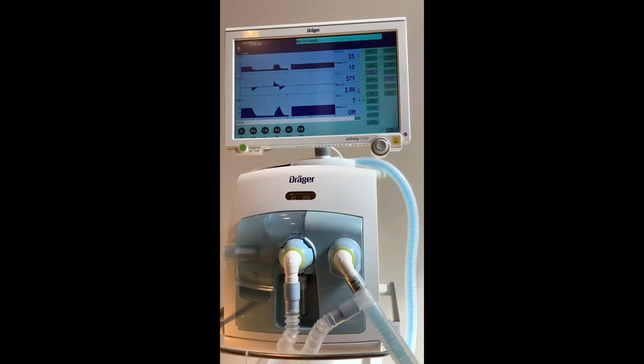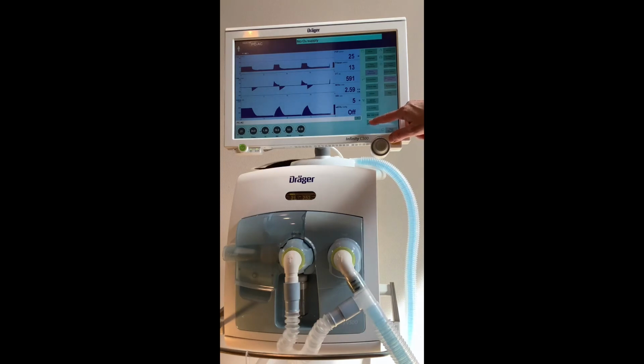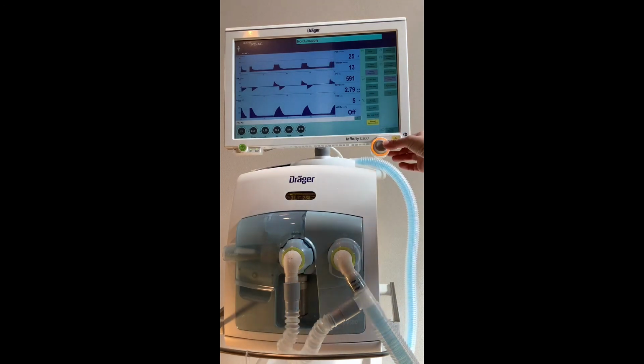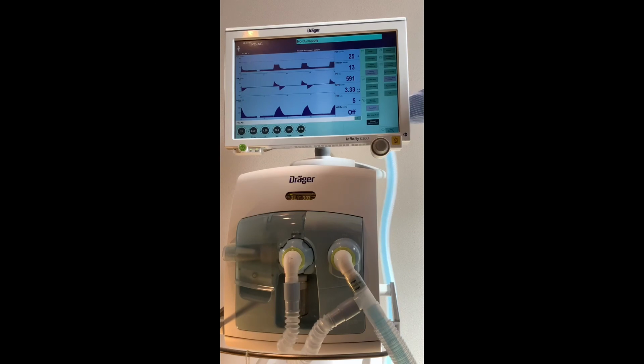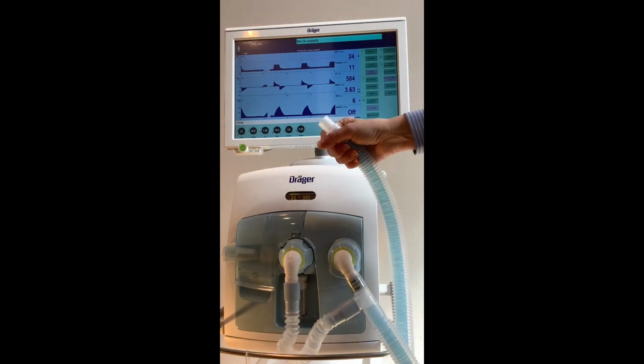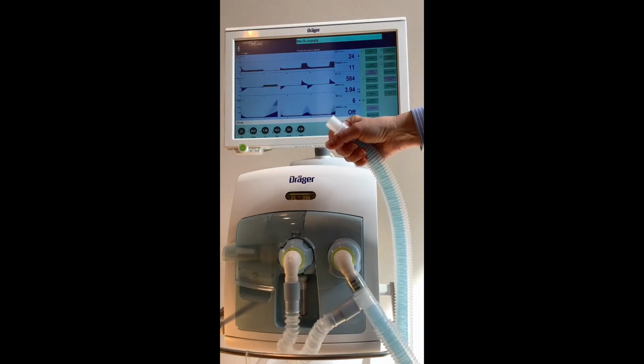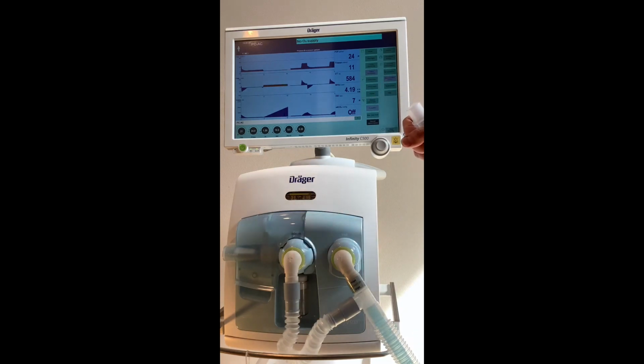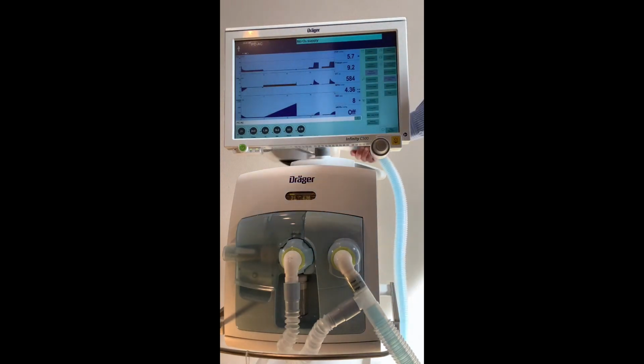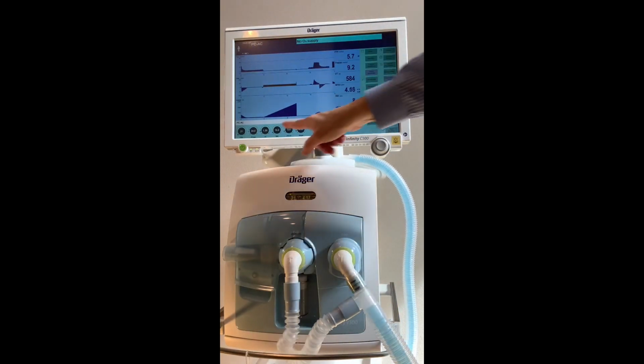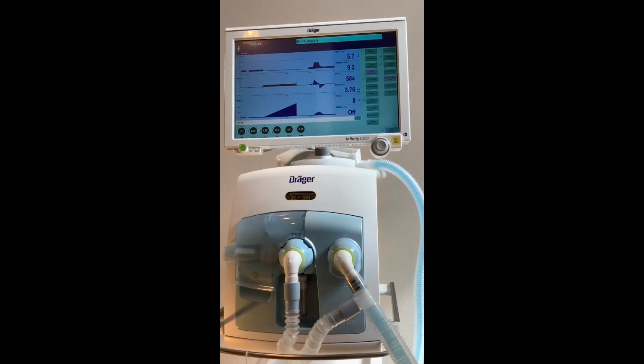Manual disconnect allows the user to set up the ventilator for a disconnect and prevent any shower of air into the room. Simply touch the manual disconnect button and confirm. And as soon as the patient is disconnected from the ventilator circuit, there's no air shower, there's no alarms from the ventilator, and this will last for up to 2 minutes. As soon as the patient is reconnected to the ventilator circuit, the machine regains ventilation at the set parameters.